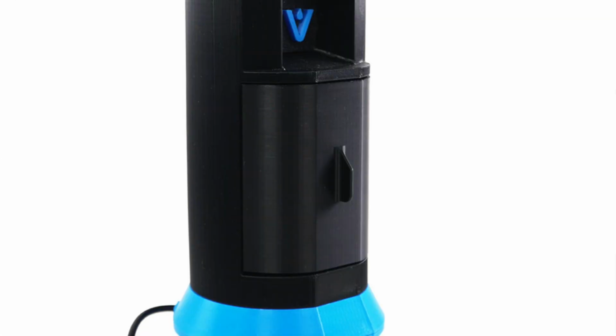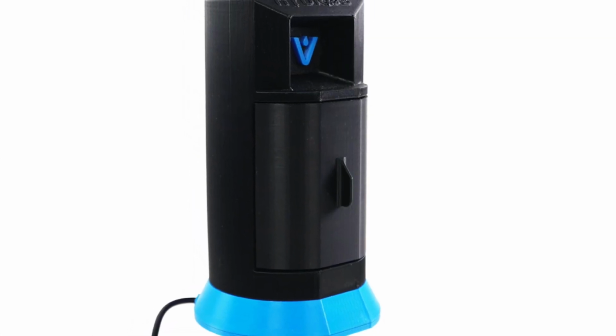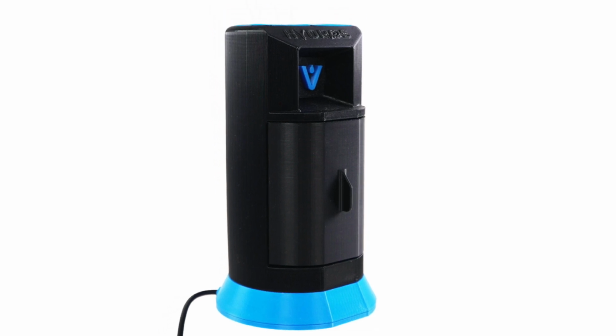So one of the biggest things I like is it comes with the little door on the front. Yes. And during this whole testing phase we went through, mine sits in a room with lights on, and I was noticing a film that would build because there's always water inside. And I'd have to keep cleaning it because the film would get in the probe. But then I noticed if I kept that in the dark, I didn't get any film. So we include this nice little door that comes on the front. Yeah, it shields the water sample and the wet surface inside the glass from the ambient light.